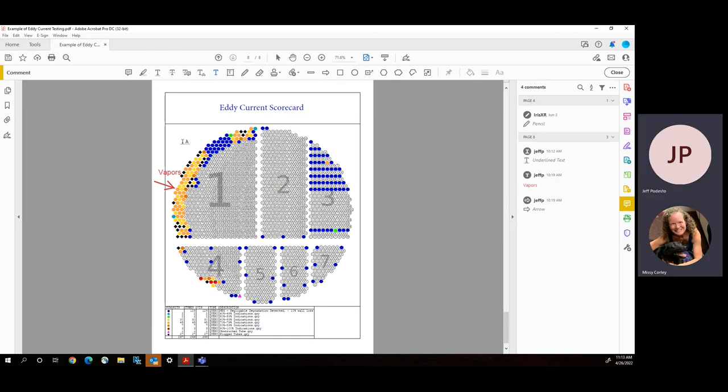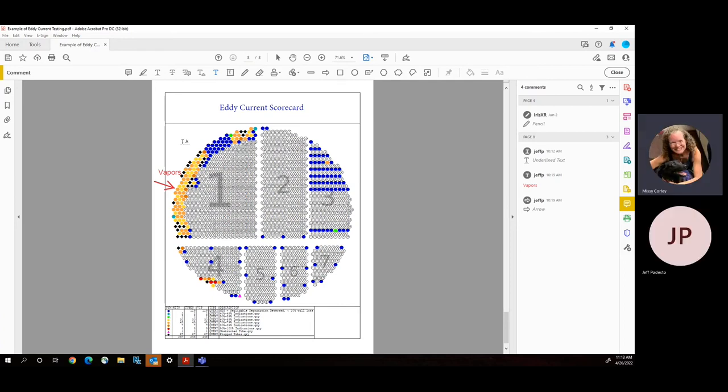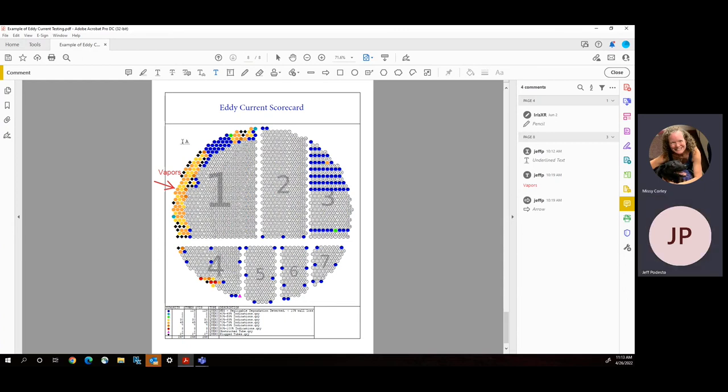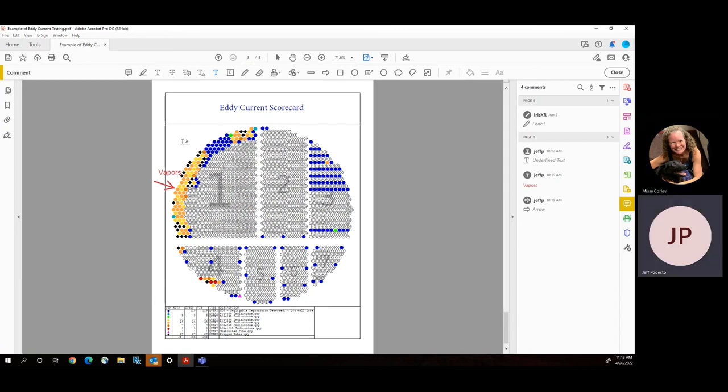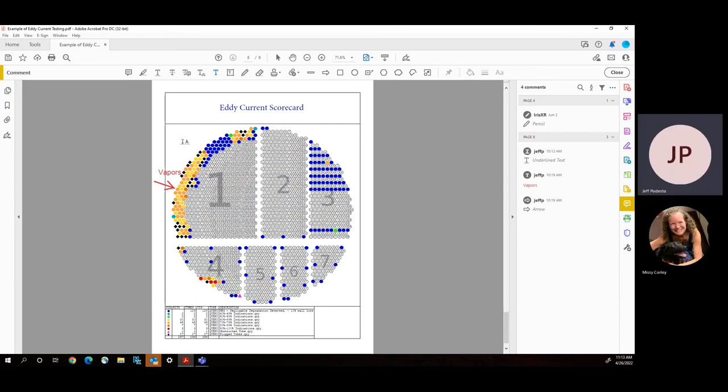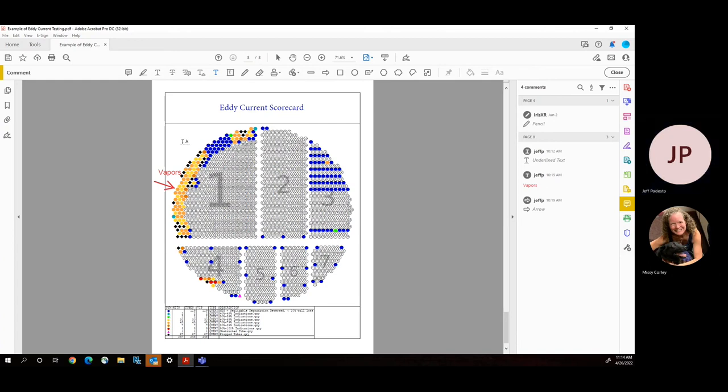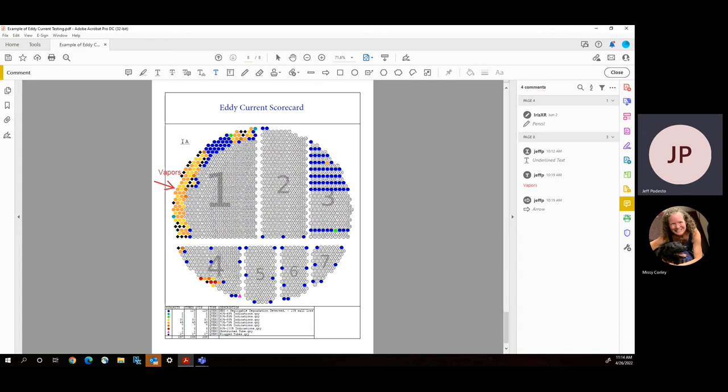All right. Well, thanks, Jeff. I have a few questions in lieu of having an audience live with us to be able to ask them. In this particular scorecard that we're looking at right now, there's a lot of tubes that don't have any color associated with them. Is that because those particular tubes were not tested? Yeah, that is the case. That's a good question. Typically, we can do 250 to 300 tubes in a day. In this case, customer had only one day to give us. So, we had to kind of target particular areas with the hope that we would be able to find where the problem areas are and where there may not be problems. And in this case, we're actually going to go back and do another day's worth. And we're going to spend most of our time on that first section determining how deep the damages are so that we can refine exactly what tubes should be plugged going forward for the customer.